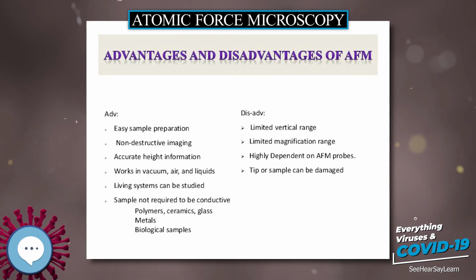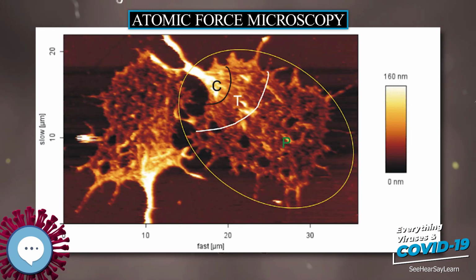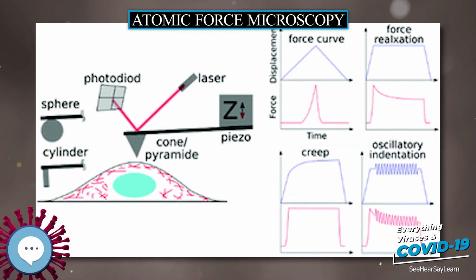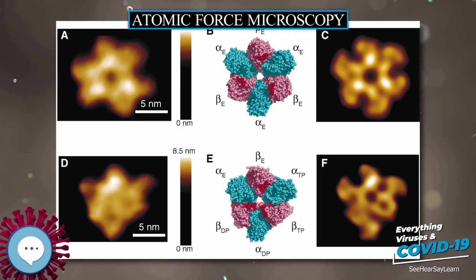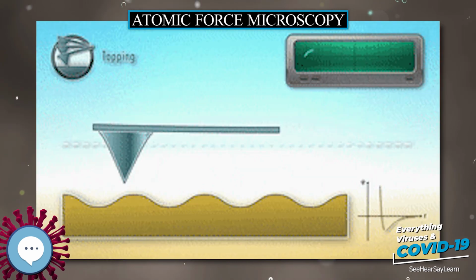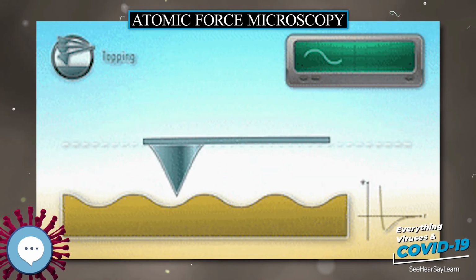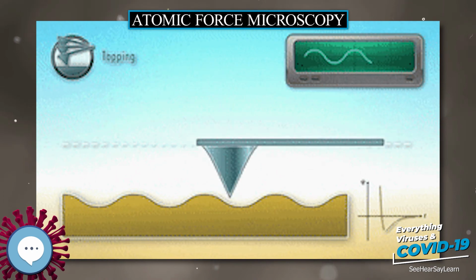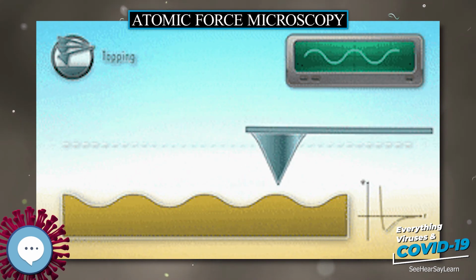When the sample has concavity and convexity, the distance between the tip apex and the sample varies in accordance with the concavity and convexity, accompanied by a scan of the sample along the XY direction, without height regulation in the Z direction. As a result, the frequency shift arises. The image in which the values of the frequency obtained by a raster scan along the XY direction of the sample surface are plotted against the XY coordinates of each measurement point is called a constant height image.